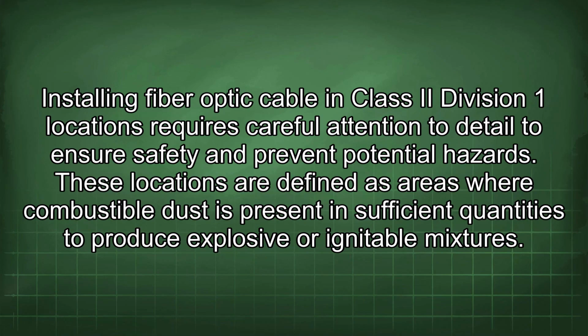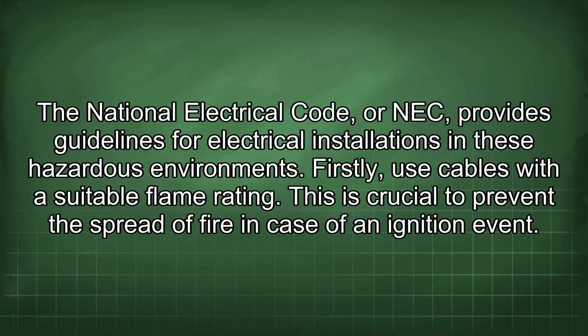Installing fiber optic cable in Class Roman 2 Division 1 locations requires careful attention to detail to ensure safety and prevent potential hazards. These locations are defined as areas where combustible dust is present in sufficient quantities to produce explosive or ignitable mixtures. The National Electrical Code, or NEC, provides guidelines for electrical installations in these hazardous environments.